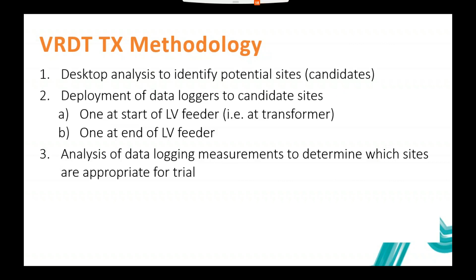From a larger pool, the way that we selected was we wanted to use transformers that were currently either overutilized or were in poor condition and needed to be replaced anyway. So we said we need to change these transformers anyway, so why don't we change them with a tap changing transformer. We also wanted a pretty large voltage drop across the LV network, which we could test with simulation software, and also a high penetration of PV on those feeders relative to the size of the transformer.